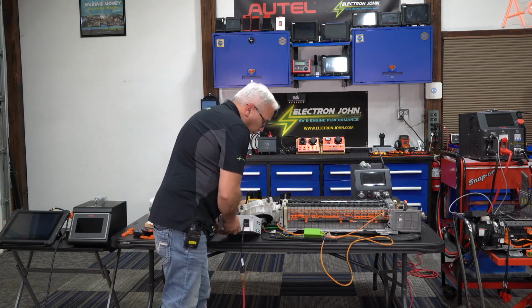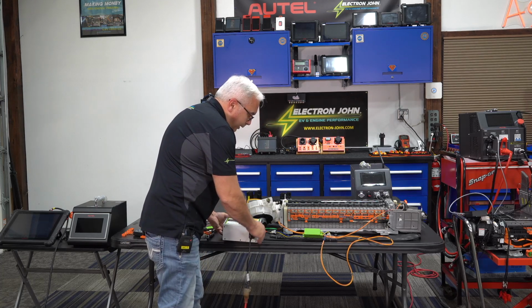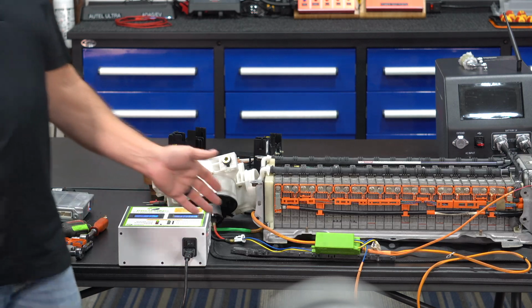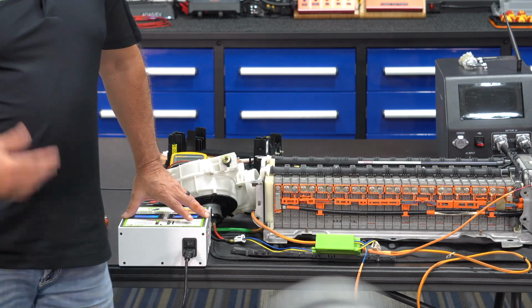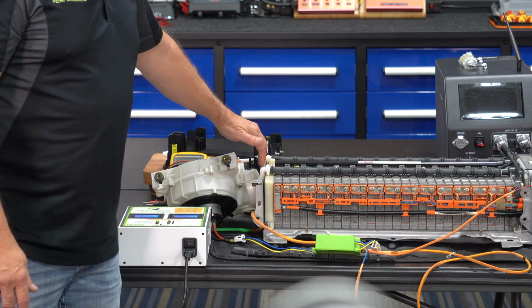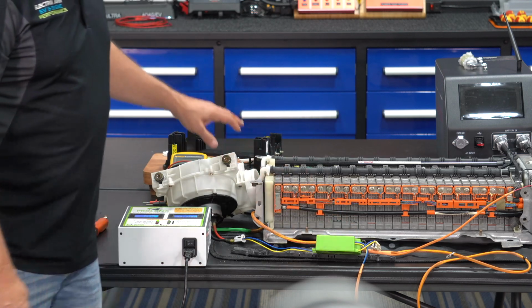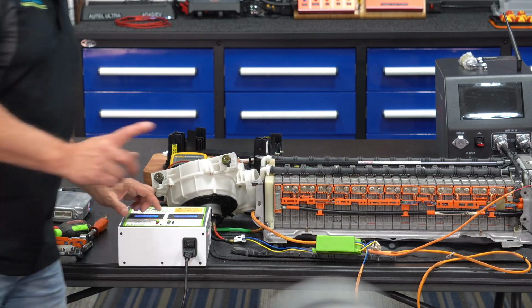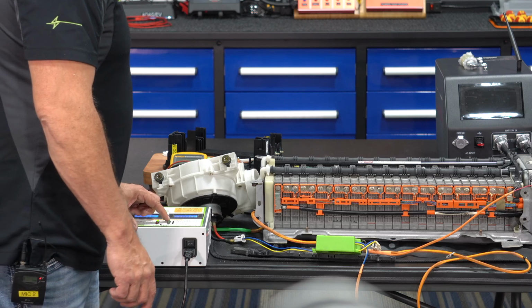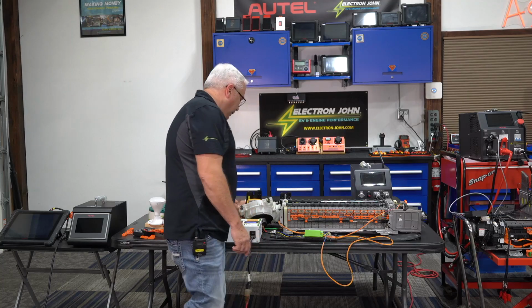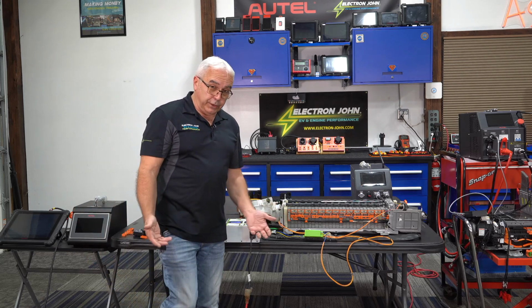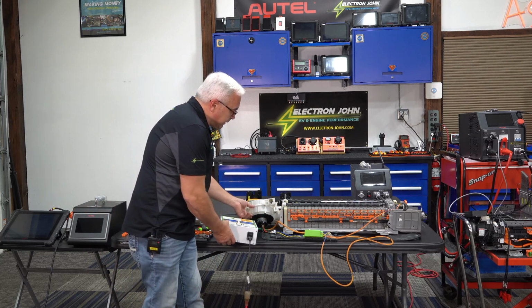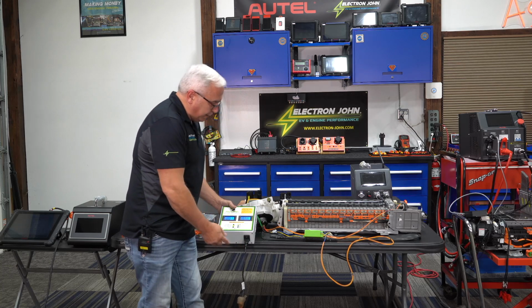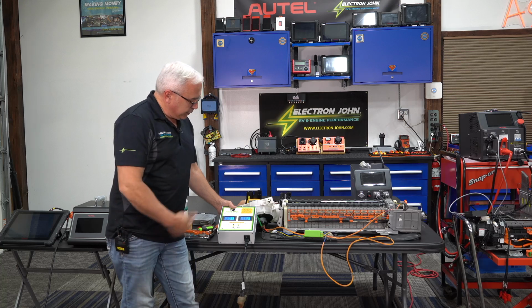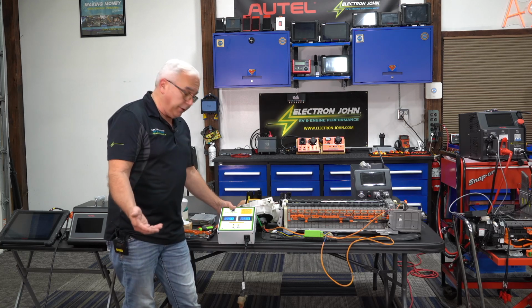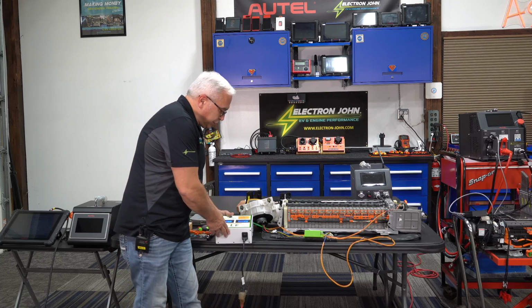So at this point, we've got the tool plugged in, we hit the power button here, and the tool's going to have two different LED displays. One is a voltage display, one's an amperage display. I've got the blower motor running because the box is doing its job here, so we're circulating some air through. And I'm going to hit the first button, which is discharge termination of 134 volts. We're starting off with a voltage of 208 volts, and we're going to stop the balancing process, and we can actually start charging it once it goes down to 134 volts. So now we're at 207 volts, so you can see we started at 208, how quickly this has the capability of discharging the battery.